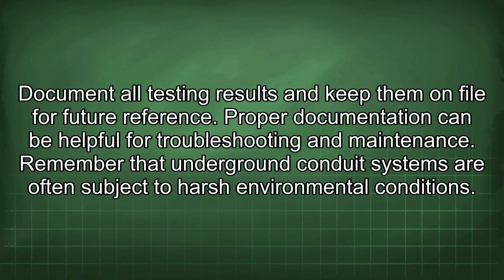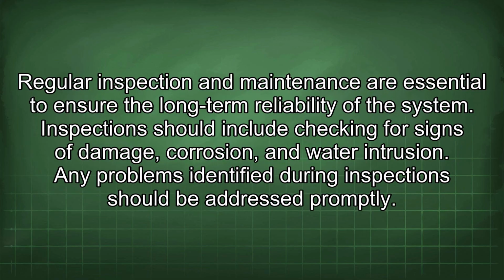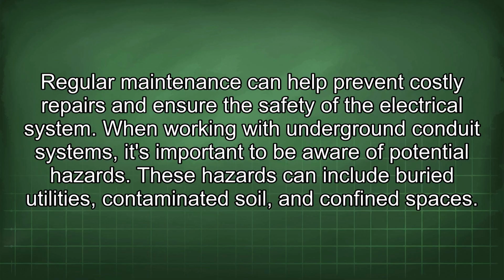Remember that underground conduit systems are often subject to harsh environmental conditions. Regular inspection and maintenance are essential to ensure the long-term reliability of the system. Inspection should include checking for signs of damage, corrosion, and water intrusion. Any problems identified during inspection should be addressed promptly. Regular maintenance can help prevent costly repairs and ensure the safety of the electrical system.